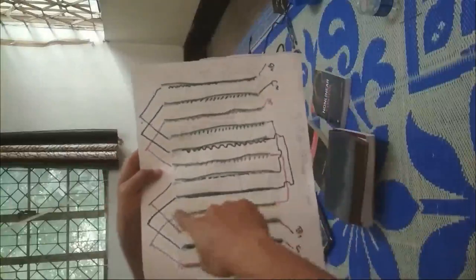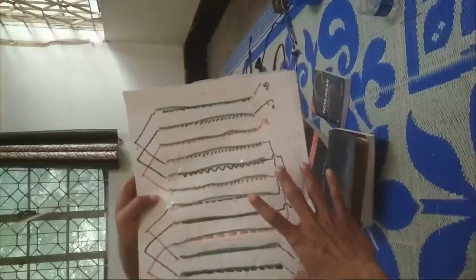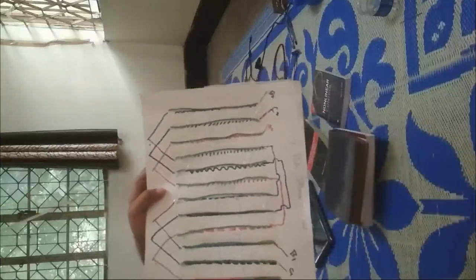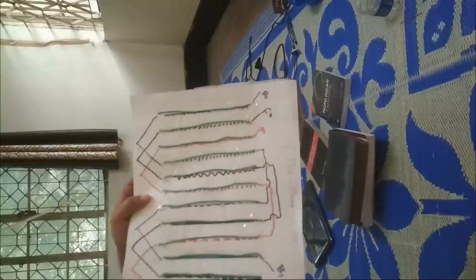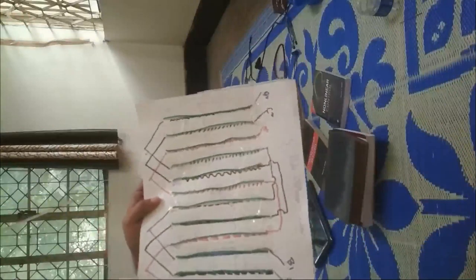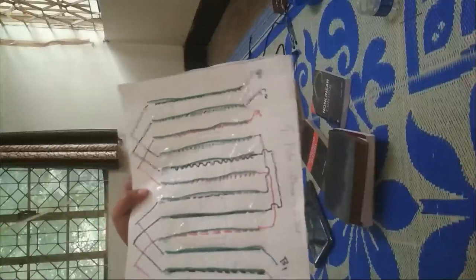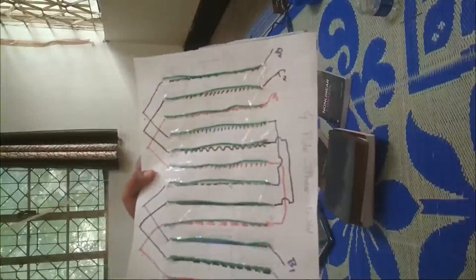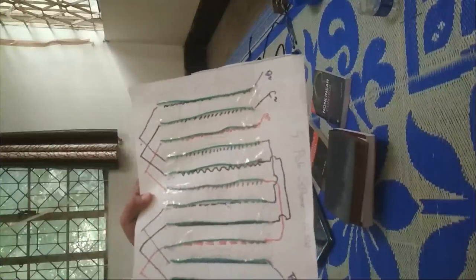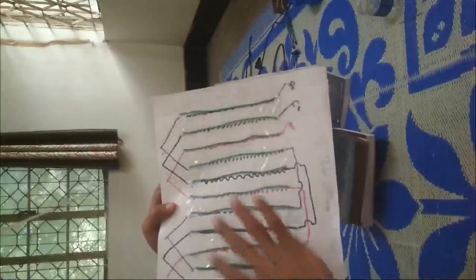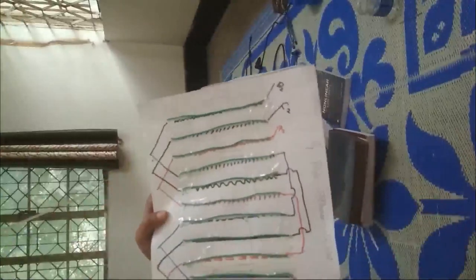After connecting the 4 conductors of A in series, we are having 2 conductors for A. Now remember, for the stator, 6 stator winding terminals must come out of your machine housing. Like if you recall the 3-phase transformer, if it is a 3-phase 3-wire connection, or we are connecting three transformers, there are always two terminals for each transformer and we are having a total of six terminals. So here also, out of these 12 slots, 12 conductors, you have to take six out of them.